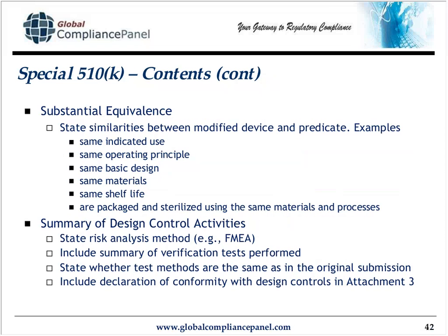In the substantial equivalence section, you list similarities and differences between the two devices. I like to include a dozen characteristics, and when only 2 of them have changed, it really illustrates to the reviewer how little has changed between the 2 devices. I find that's much more effective than merely listing those 2 things that have changed. I like to include what has remained the same as well.